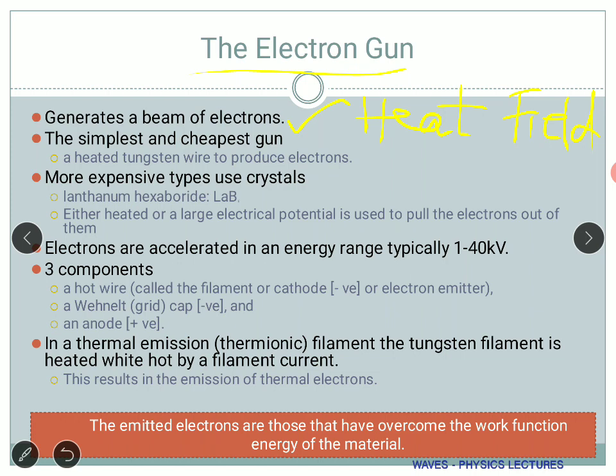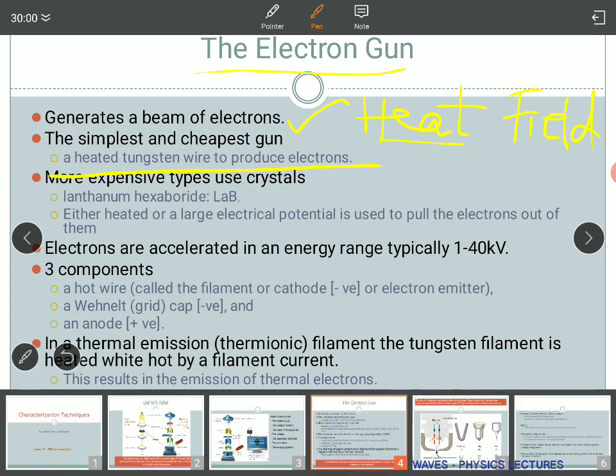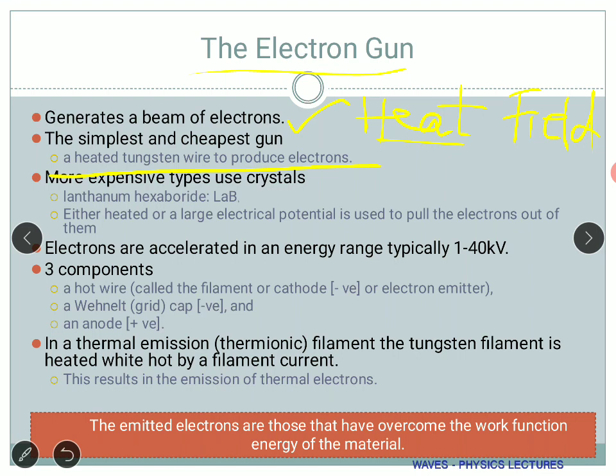The simplest, cheapest and widely used electron source is tungsten wire — we heat the tungsten wire to produce electrons. If you want a better setup, you use a more expensive crystal which is lanthanum hexaboride (LaB6). Lanthanum hexaboride is heated, or we use a large electric potential to pull the electrons out. The electrons are accelerated in an energy range typically of 1 to 40 kilovolts.